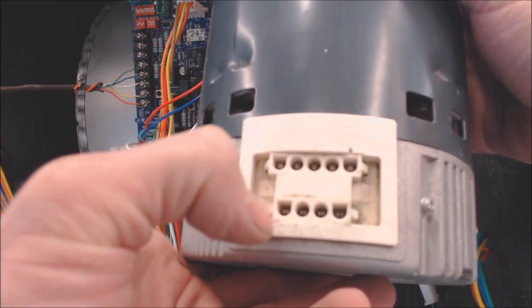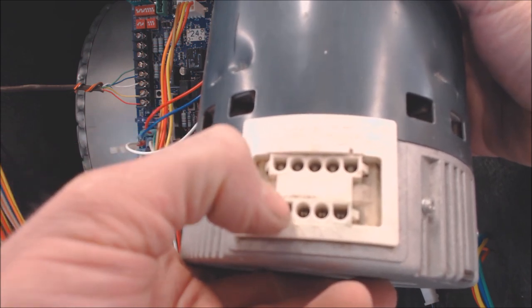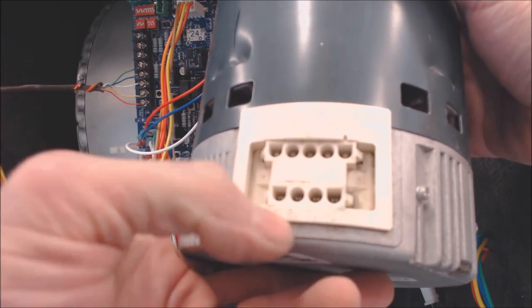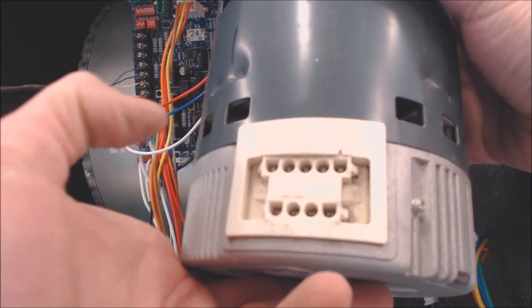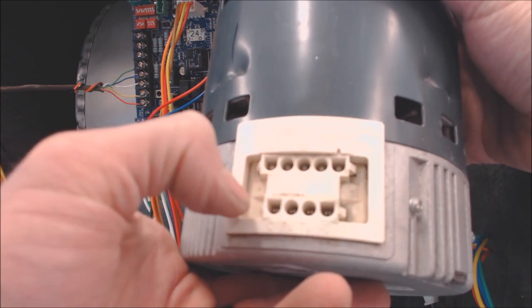So you can have the hot go in R and the common go in C. Or you can actually have the 24 volts go in the C and common go to the R. It does look like though that you should put the 24 volt hot in the R and common in the C. So I would recommend just going ahead and doing that if possible.